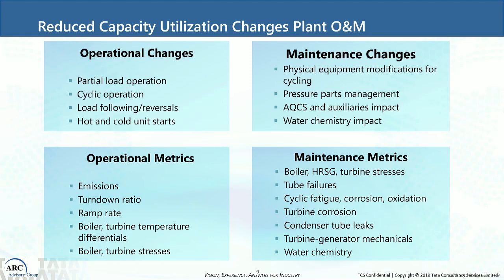The key operational metrics are going to change. Emissions is always a key metric, but it will be much more difficult given the far less steady state operation. Turndown ratio of a plant or unit will become more important to support stable partial load operation. And ramp rate will become important to follow dispatch schedules without overstressing equipment. Equipment temperature differentials and mechanical stresses are far more important in these kinds of dynamic cyclic operations than they are in steady state operation.